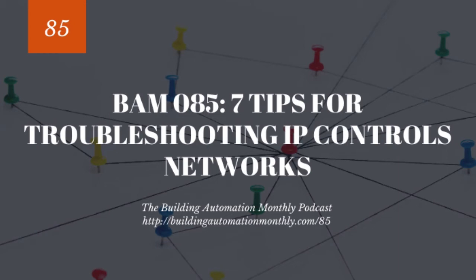Then you want to verify power. One of the things about these new IP controls is that if one of them loses power, then especially on the daisy chain architecture, it's not going to continue that pattern. You can't see me moving my mouse up and down making a daisy chain, but I realize you can't see what I'm doing, so envision hop after hop after hop, just like MSTP. But unlike MSTP, that is a powered communication, this is going to need that boost of power at the network interface card on the controller to make it work.